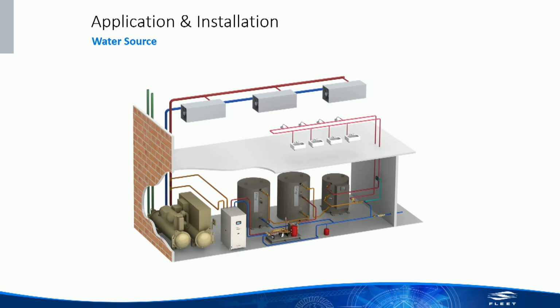These systems will work. And similar to what we saw in the past presentation, we're going to have multiple tanks typically in series to improve stratification and have a very high lift on our CO2 heat pump. We're typically going from 40-degree or 50-degree incoming domestic water from the street and putting out that 170 or 180-degree water into the tank, so a very high lift. Unfortunately, that is the one benefit, but at the same time, detractor to CO2. It wants a really high lift, so it's a great application for domestic water.